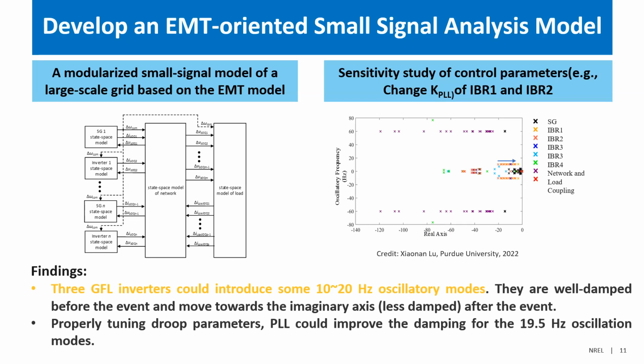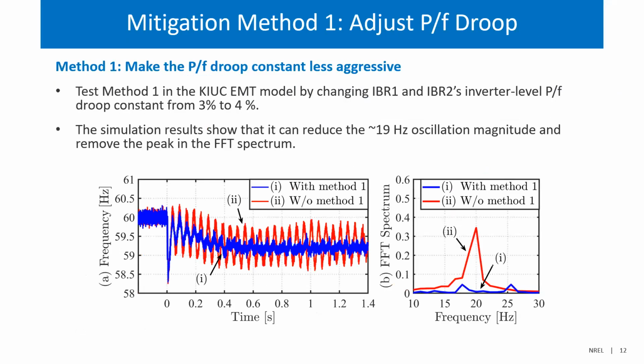After identifying that, we needed to validate it, since the small signal model is based on a linearized model and we didn't know how effective it would be. So we went back to our EMT model and tried the first mitigation method: adjusting the PF droop. We tested it, changing the PF droop constant from 3% to 4%.